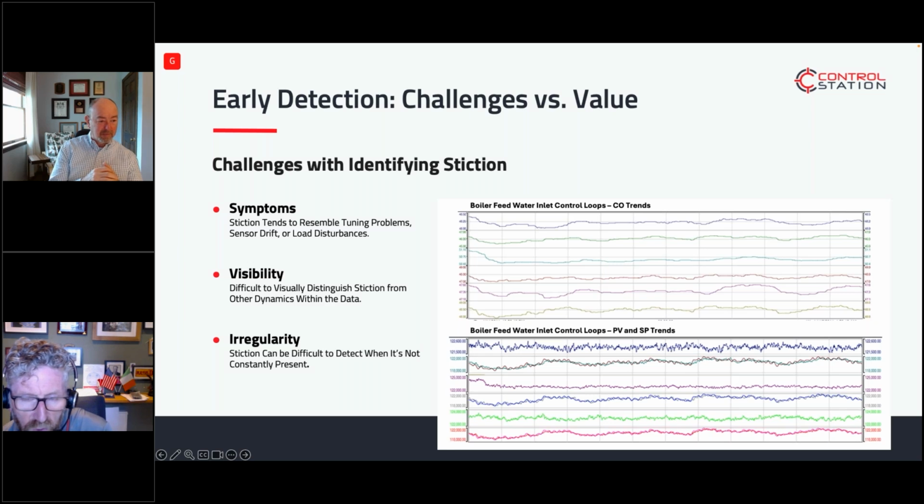Yeah, it's absolutely so. You can understand your process is oscillating, but why is it oscillating? I see our PVs are moving around, but which ones are problems, which ones are tuning, etc. It's going to lead you down a number of garden paths until you diagnose it. You need tools to give you a point of focus, I suppose.